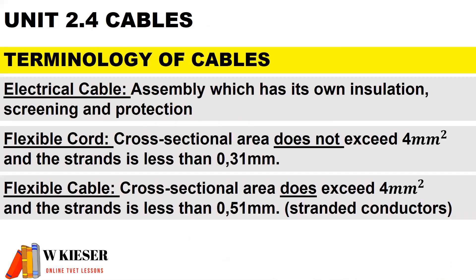The terminology of cables. An electrical cable is an assembly which has its own insulation, screening, and protection. A flexible cord has a cross-sectional area which does not exceed 4 mm², and the strands are less than 0.31 mm. A flexible cable has a cross-sectional area which does exceed 4 mm², and the strands are less than 0.51 mm.